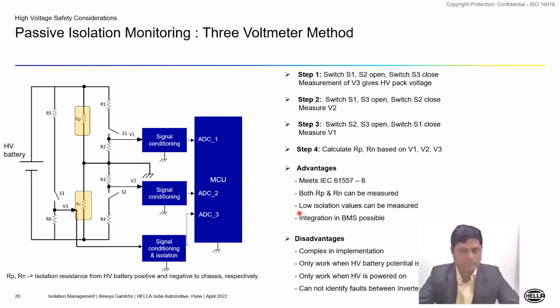This method will meet the IEC 61557-8 requirements. Both RP and RN can be measured. But the challenge with this method is complexity because of changes in the DC voltage. It will work only when the HV battery potential is stable, meaning the vehicle is not moving, and only when HV is powered on.